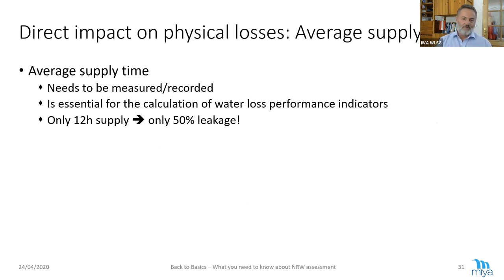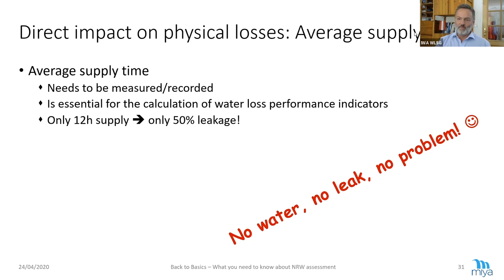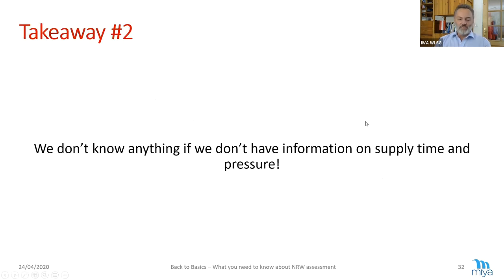Supply time — very often forgotten. I once spoke to a young engineer from an Indian water utility who told me, 'We are very good — we have only 20% leakage.' I said, congratulations, that's great. So what's your supply time? 'Oh, we have two hours every second day.' Two hours every second day — imagine what your leakage level would be if you had continuous supply. We can say: no water, no leak, no problem. So this is the second takeaway: we don't know anything if we only have a water balance and we don't know the supply time and the pressure. Water balance alone does not tell us much.